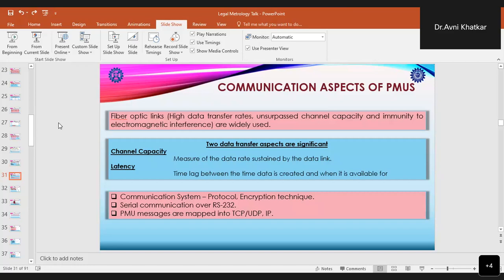When we talk about communication aspects, two data transfer aspects are very significant. That is channel capacity, which is nothing but the measure of the data rate sustained by the data link, and the latency in the measurement. Latency is the time lag between the time the data is created and when it is finally available. So these two aspects are very significant from the communication point of view of the phasor measurement unit. And when we talk about the communication system, all the protocols and encryption techniques also come into the picture. So when we have PMUs, the communication is serial communication using RS-232, and all the PMU messages are mapped into TCP, UDP or IP.